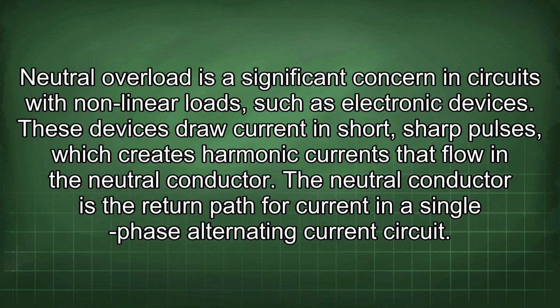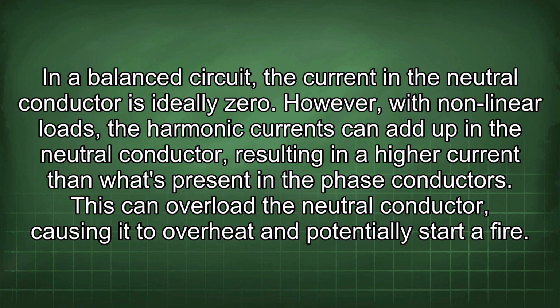Neutral overload is a significant concern in circuits with nonlinear loads, such as electronic devices. These devices draw current in short, sharp pulses, which creates harmonic currents that flow in the neutral conductor. The neutral conductor is the return path for current in a single-phase alternating current circuit. In a balanced circuit, the current in the neutral conductor is ideally zero. However, with nonlinear loads, the harmonic currents can add up in the neutral conductor, resulting in a higher current than what's present in the phase conductors. This can overload the neutral conductor, causing it to overheat and potentially start a fire.